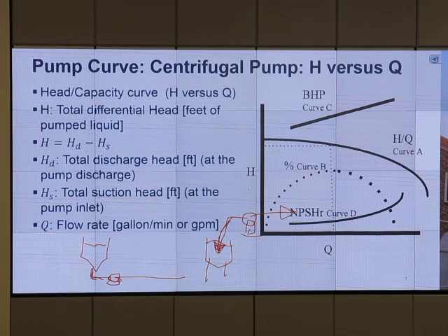A pump cannot suck it from the top. It doesn't work that way. It is not good at sucking fluid, but it's good at pumping it. So we have to help it deliver fluid to the pump. Lift the tank a little bit up, and then liquid can go down naturally due to gravity and go to the pump. Sometimes, even though your pump is at the bottom, when you turn it on, nothing happens. That kind of thing happens too, you know that? That's because you have air inside the pump. If you have air inside the pump, it's air lock.